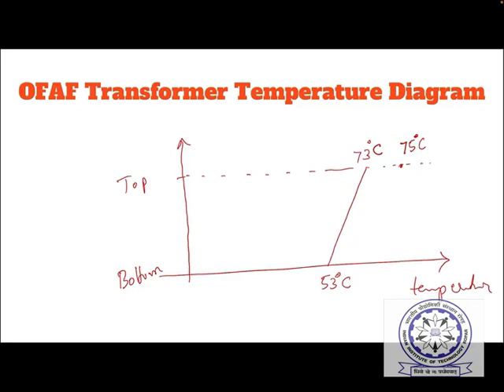Here, why this is happening, you have to understand. Through the winding, there is no difference actually. That is why, and winding is the hotter portion. Therefore, it dominates in deciding the temperature within it. So 53 to 73, more or less same as the previous case, even though oil is circulated now. But within the oil there will be huge difference. So the point C will be again at higher temperature only. So the difference is more or less same.